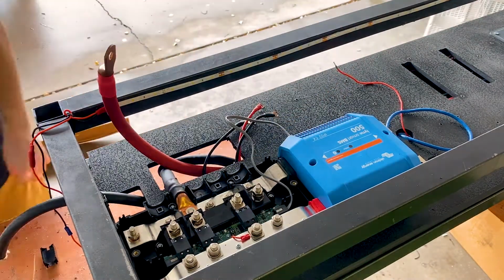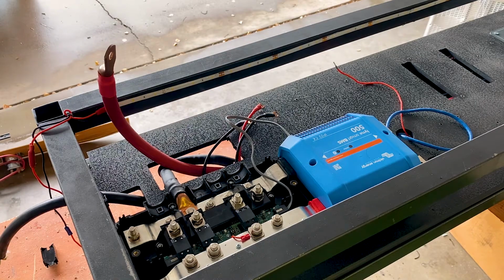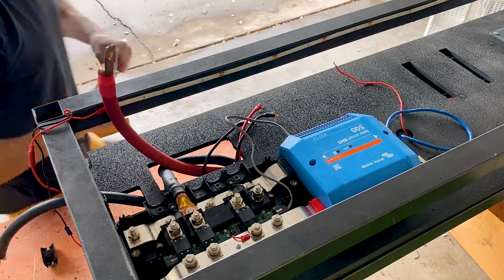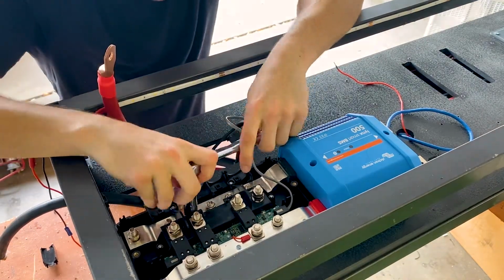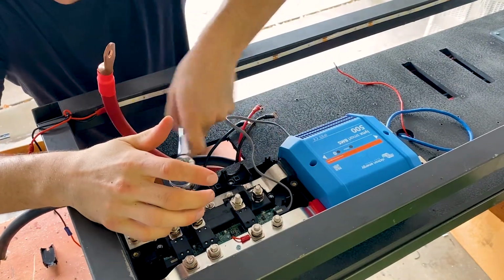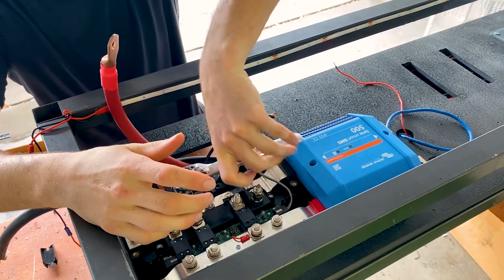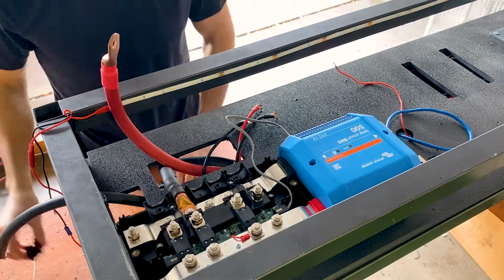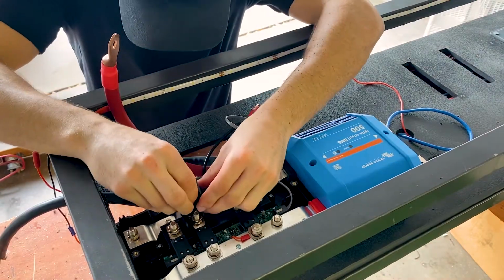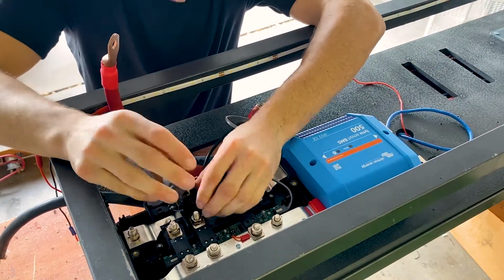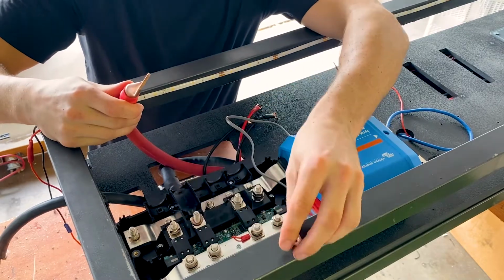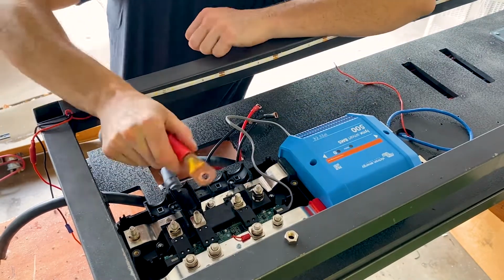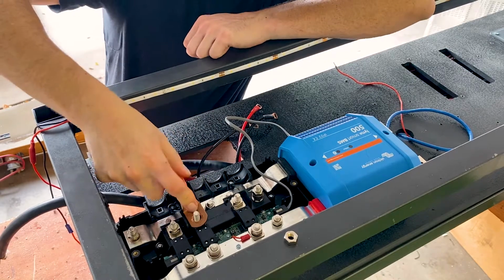The inverter is going to get a 400 amp mega fuse. The dual DC to DC chargers will get a 100 amp mega fuse. We'll tighten it with our hands first and then come in later with a socket to make sure it's nice and tight and secure, making that negative connection first. Put the cover separating the positive and negative terminals, and then go ahead and make that positive connection like this.